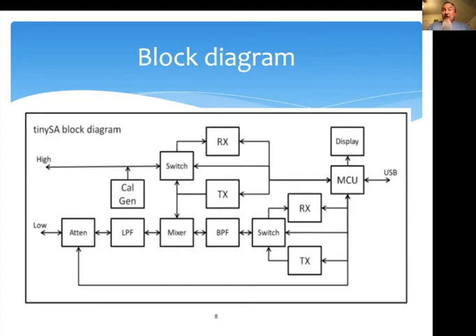Okay, calibration on this is dead simple. You run one calibration test whenever you feel like it to check the accuracy of the frequency display. It then runs through a series of 8 self-tests internally, and if they all come out green light, you're ready to go. That's all you have to do. Operating this device is not about regular calibration. It is all about watching out and avoiding those artifacts and spurious signals. So that's something I want to emphasize there.